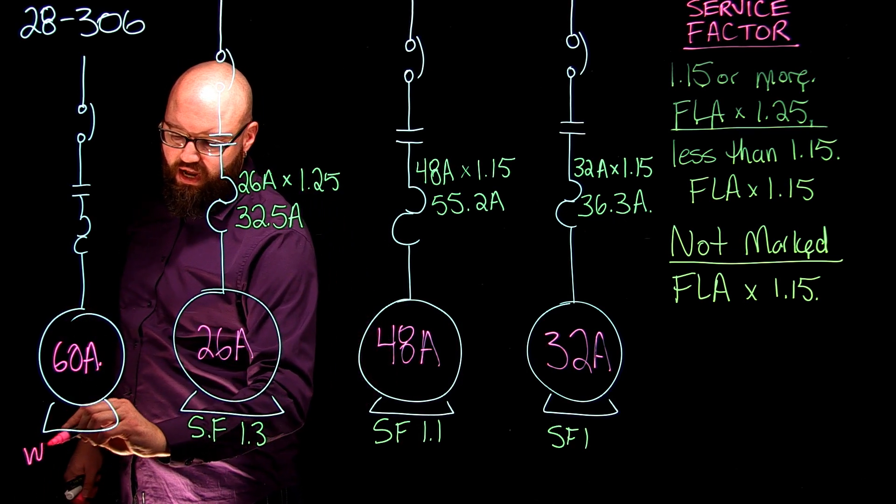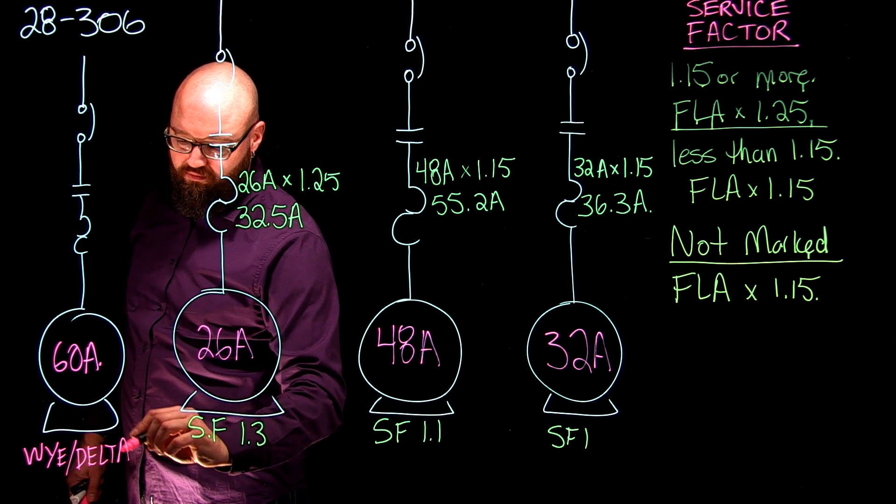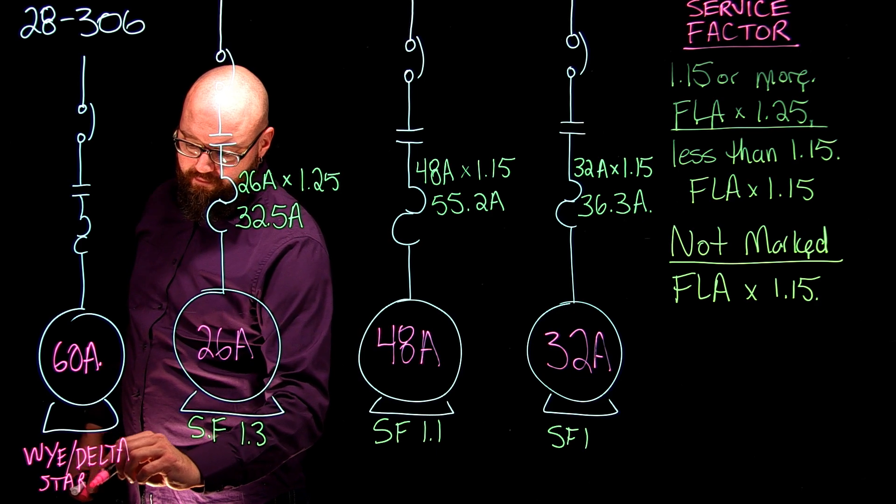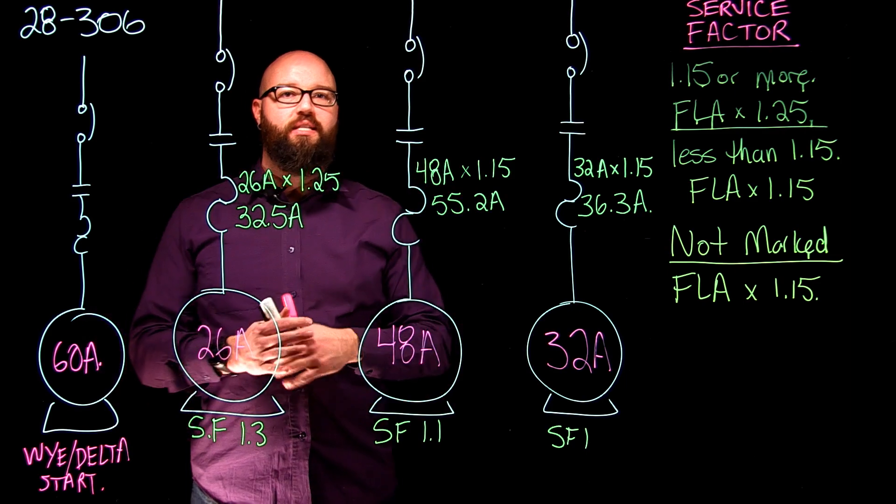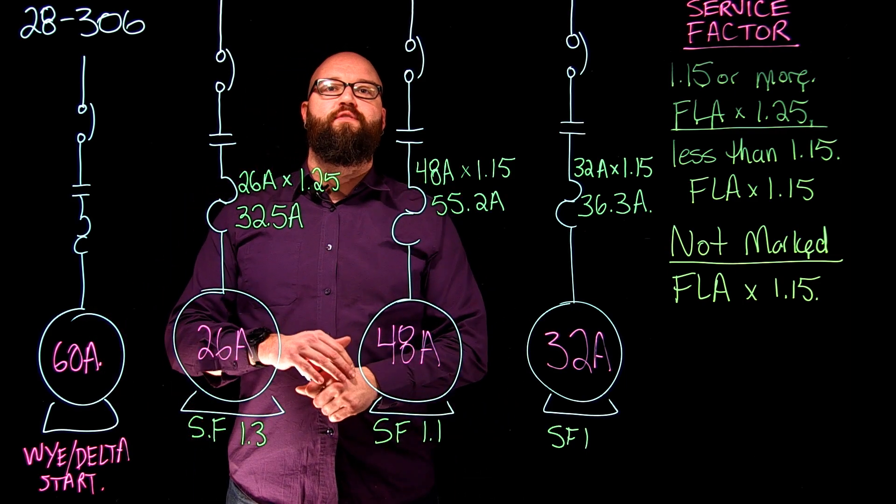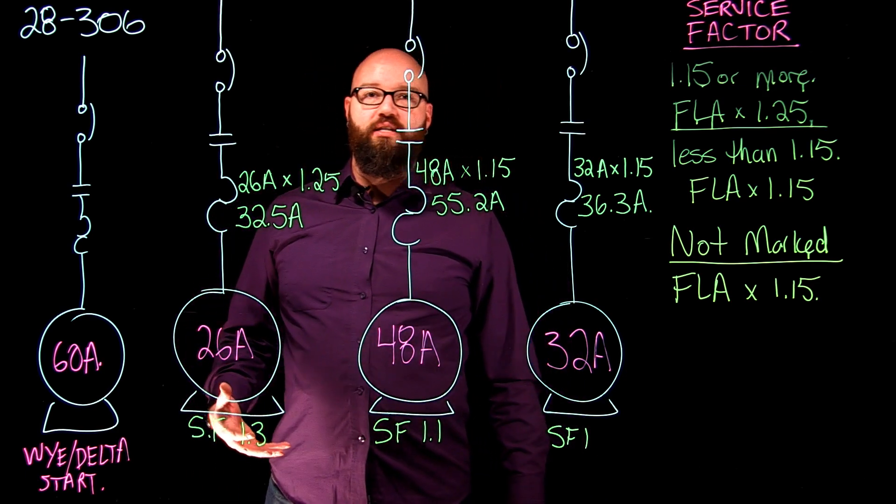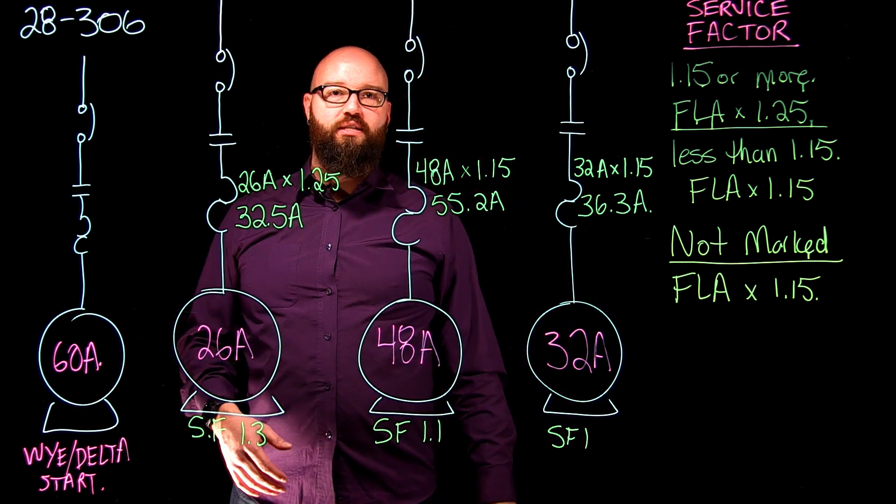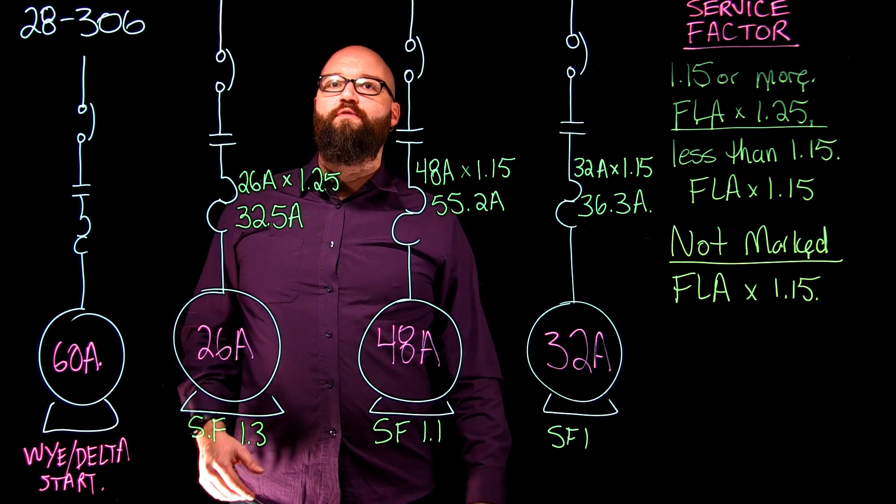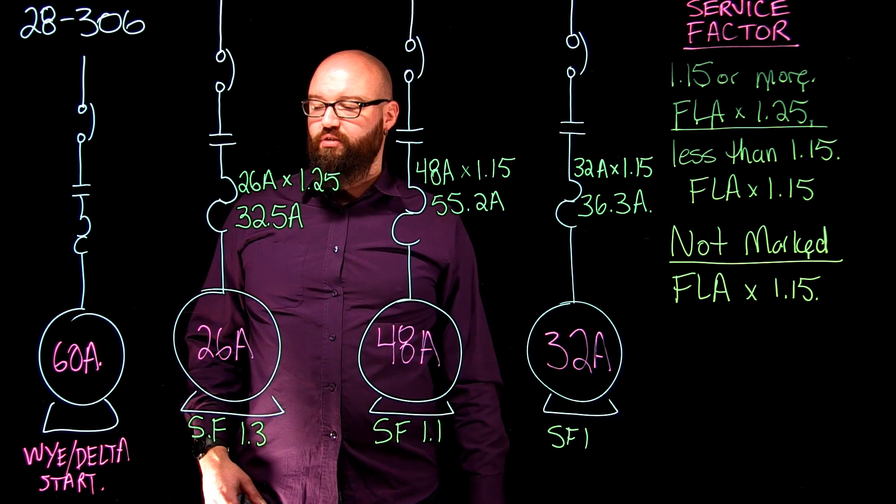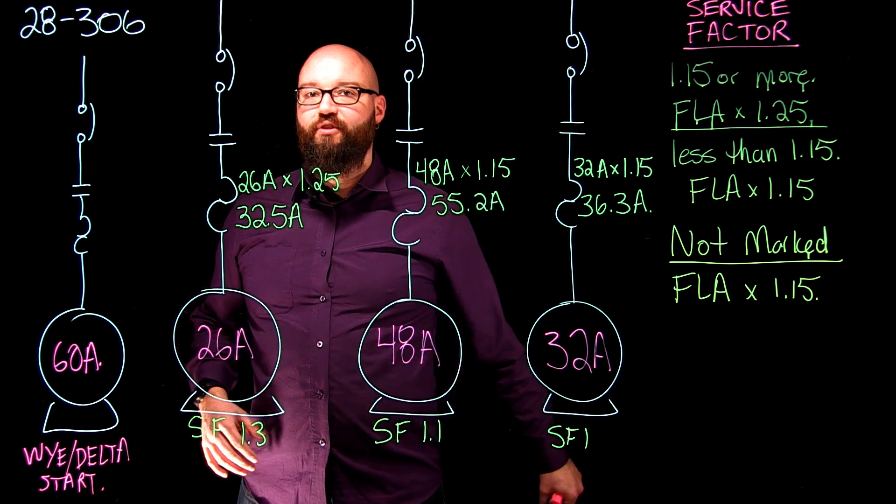We are going to put an FLA on this one of 60 amps. But this motor is a little bit more specific. We're going to say that this is a Y-delta start, which means that our motor is going to start in a Y configuration and then once it gets up to a certain speed or a certain duration of time has passed, it's actually going to switch into a delta configuration. It's going to run in delta. So it starts in Y and it runs in delta. What that means for us when we're sizing the overloads is the actual overloads are located within the phases, so we're going to size those based off of the phase current of this motor.